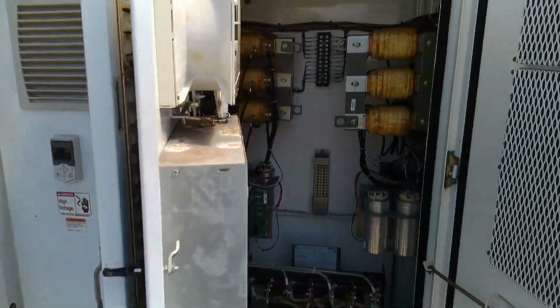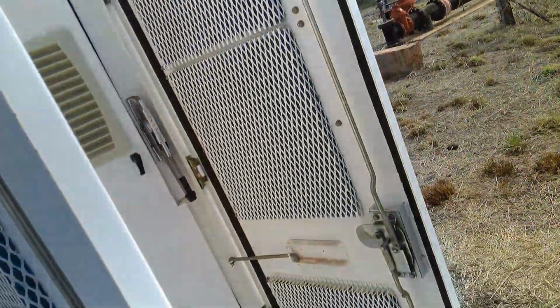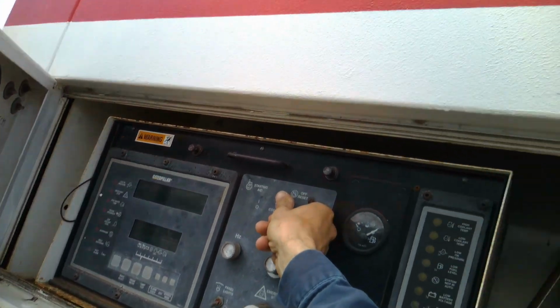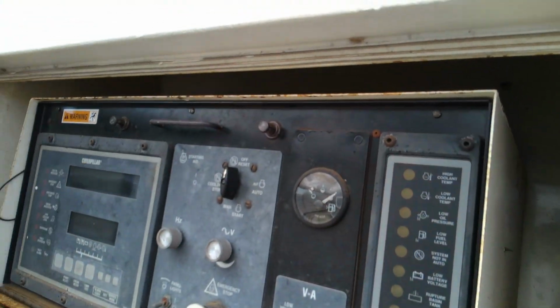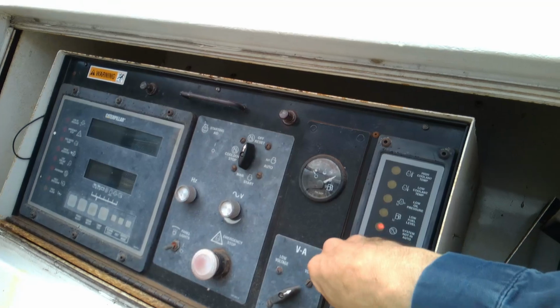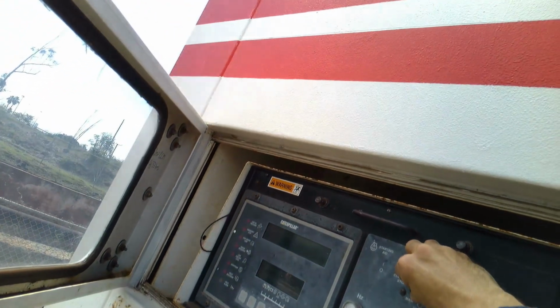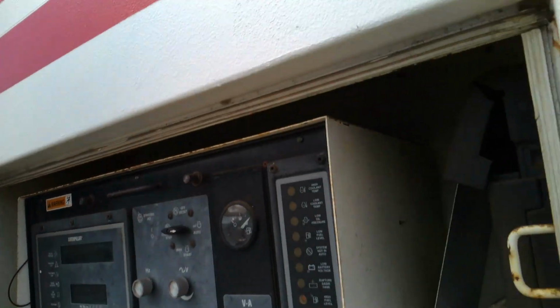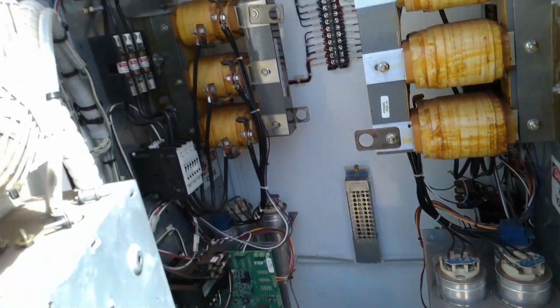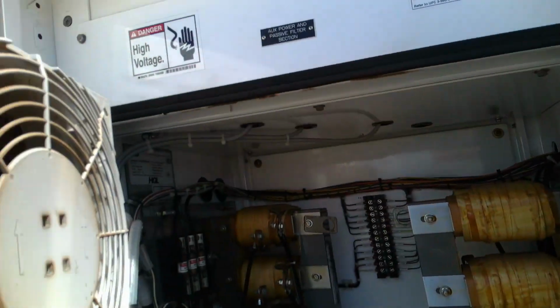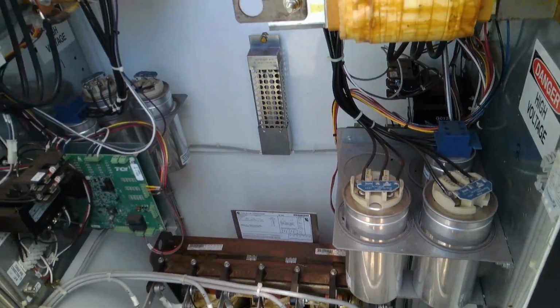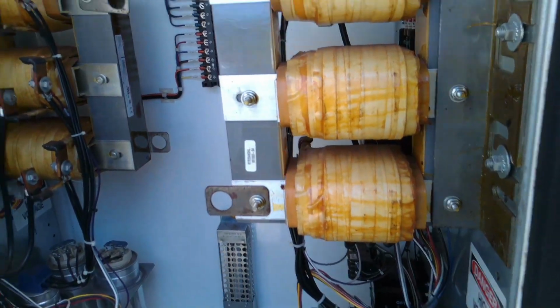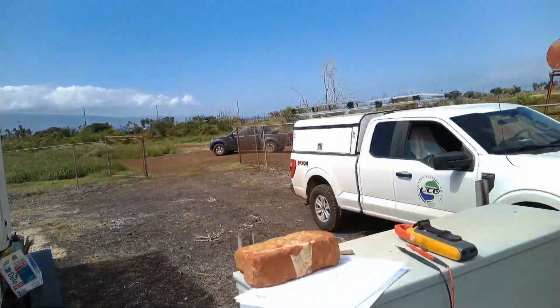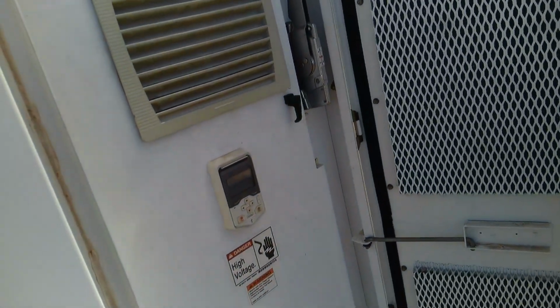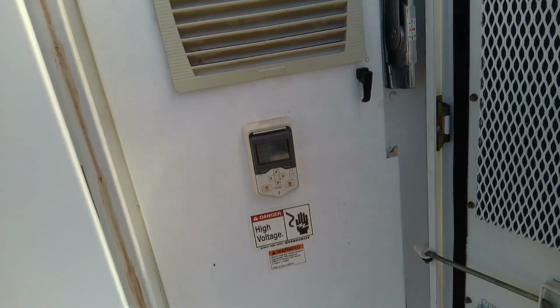Let's shut down the gen, get this cover back on, talk about what we're going to do. Okay, we'll close it up. We'll put pump 1 back in auto. Let it start up and run, make sure it's all good, and then we're done here and I can submit all this information to TCI. Pump 1 on the gen. I think it's about a 10-minute warm up and then it'll start ramping.